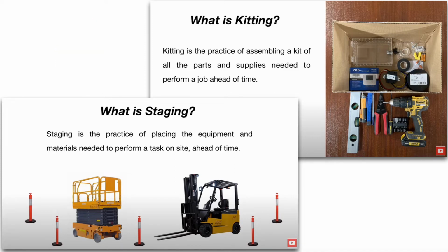And staging is a practice of placing the equipment and materials needed to perform a task on site ahead of time. So do you need a forklift? Do you need a man lift? Do you need lengths of conduit? And it's always a good idea to inspect all the equipment once it arrives to make sure it's not damaged and ready for install. So again, have everything kitted and staged ahead of time so you can hit the ground running when you do the install.